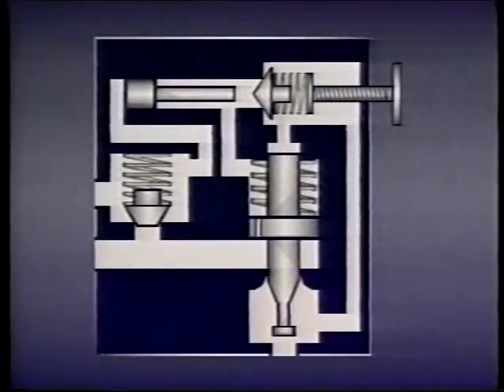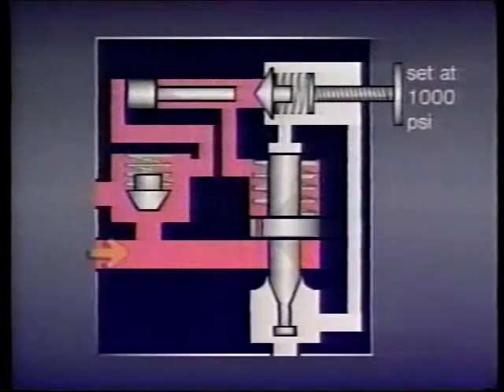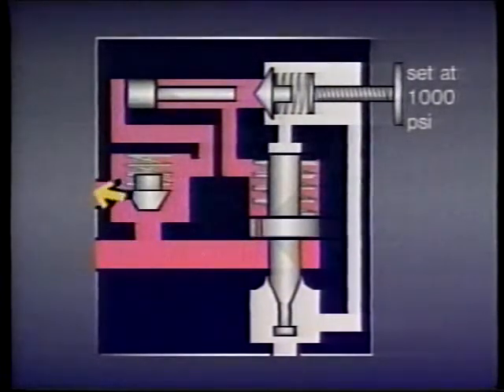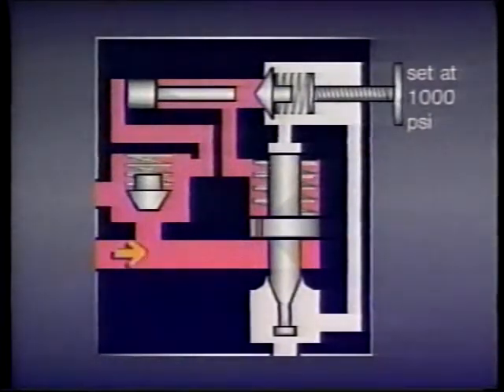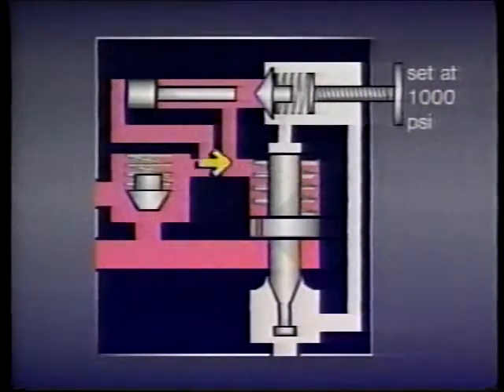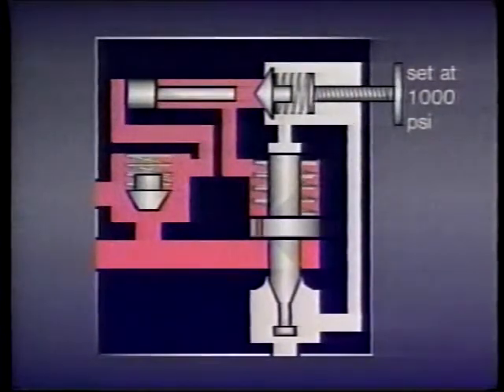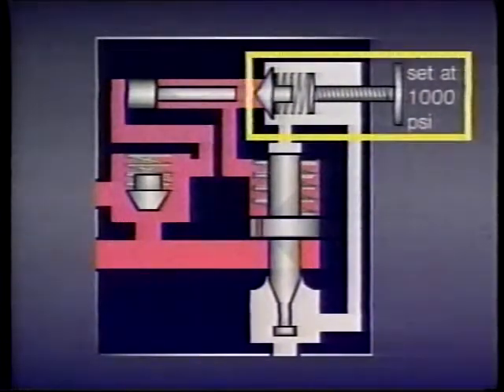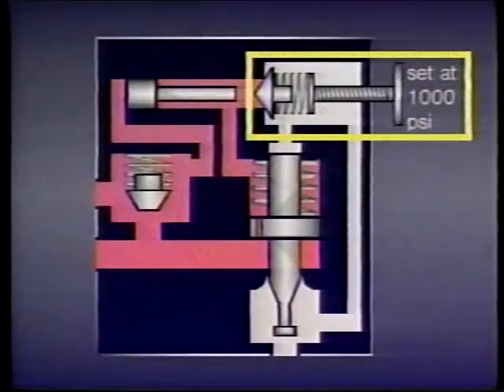Here's how it works. When the accumulator is being filled, flow from the pump — shown in red — goes past the check valve and into the accumulator, filling it with fluid. Fluid at the same pressure also goes through a pilot passage to one end of the differential piston, and through another passage to the other end of the piston and to the face of the dart. In this case the spring tension on the dart has been adjusted so the dart remains seated until pressure rises to 1000 psi.